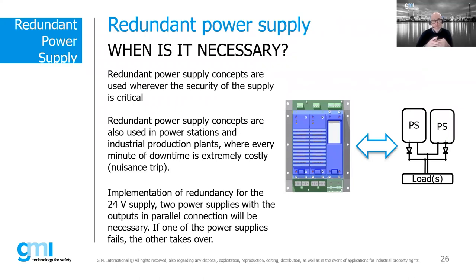A power supply redundancy system must be used when the safety of the power supply is essential. For this reason, redundant power supply systems are used in critical sectors such as oil and gas or pharmaceuticals, and in all those applications where the loss of power supply translates into the loss of sensitive information, or where the certainty of having a correct power supply on request is fundamental. It must also be used in all systems where every minute of production downtime is extremely costly.